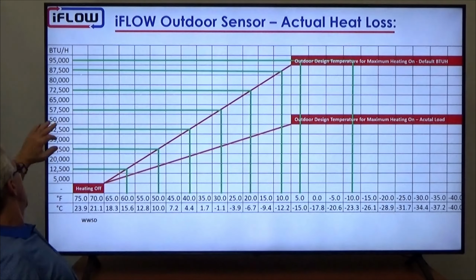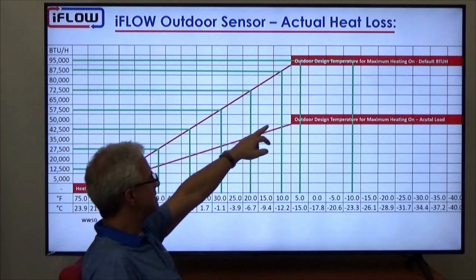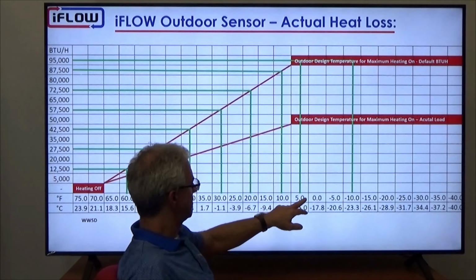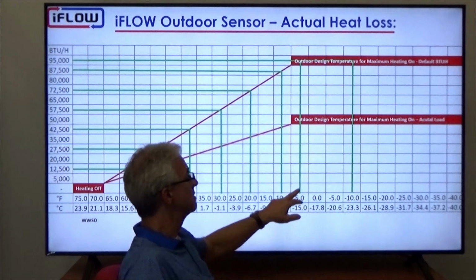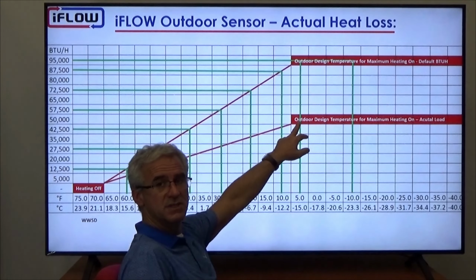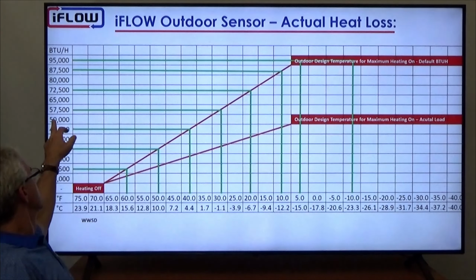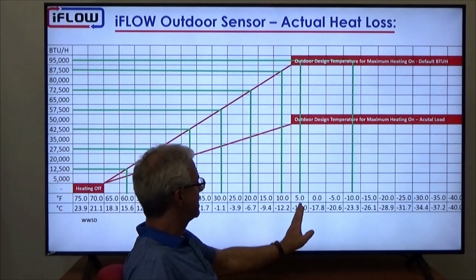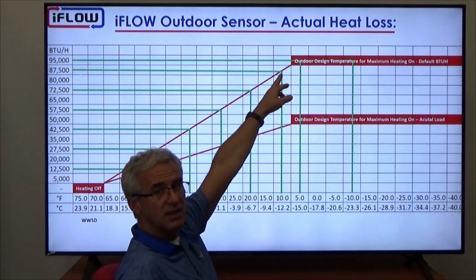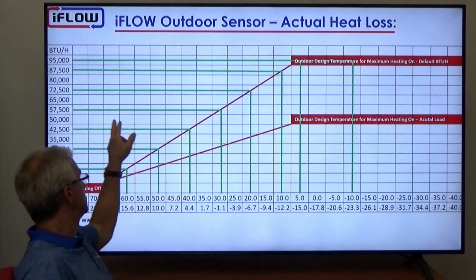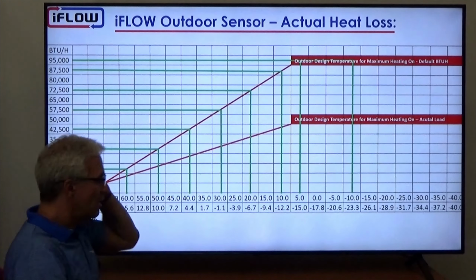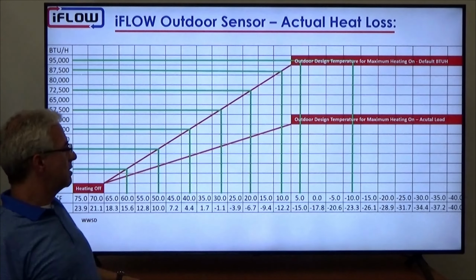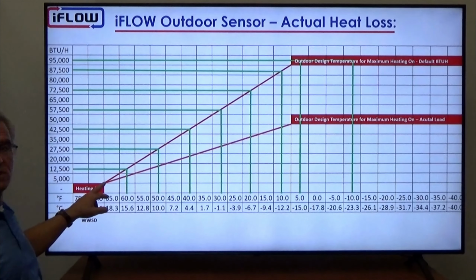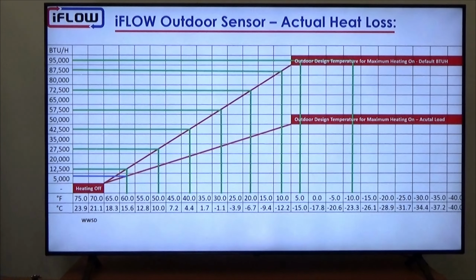So now at 50,000 BTUs, that's our outdoor design temperature. So at that 5 or minus 5 Fahrenheit, minus 15 Celsius, we have the outdoor design temperature or the heat load at 50. So we know that when the temperature gets to here, we need to deliver not 95,000 BTUs, but we need to deliver 50,000 BTUs. So if we go back, that automatically creates a different slope, and then as we go down the temperature curve, we see that we deliver lower amounts of heat.